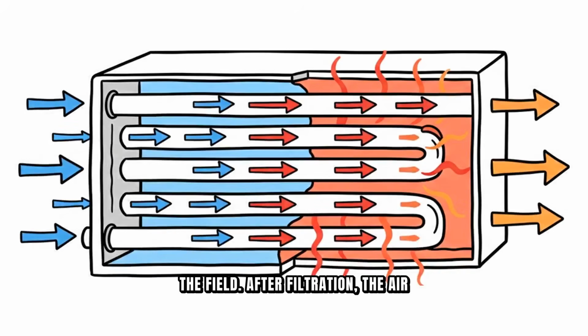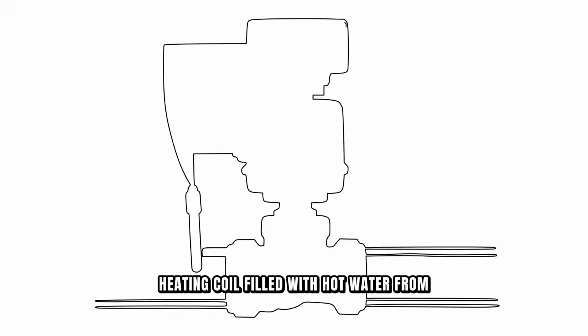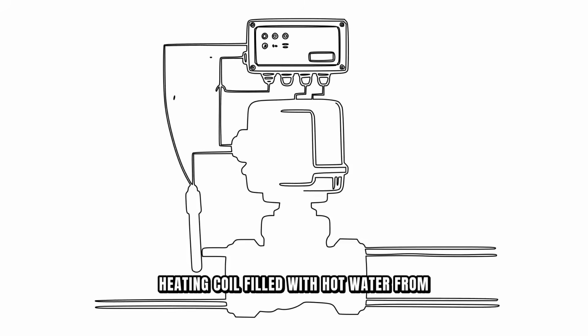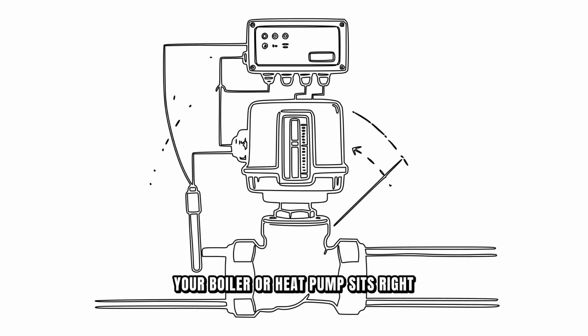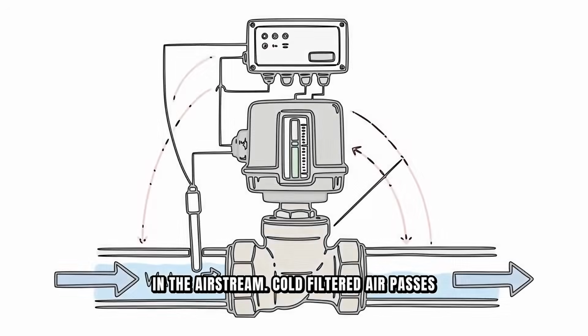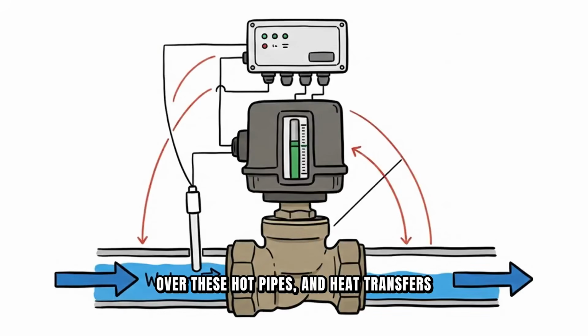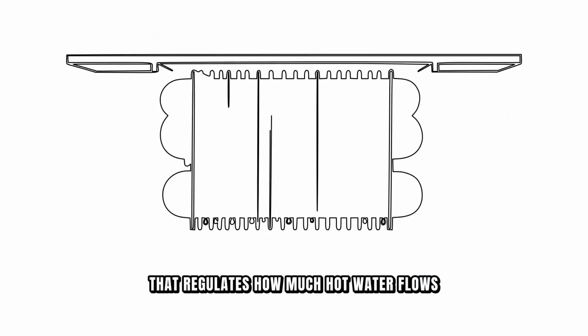After filtration, the air encounters the heat exchanger and cooling coil. Let's talk about heating first. In winter, a heating coil filled with hot water from your boiler or heat pump sits right in the airstream. Cold filtered air passes over these hot pipes, and heat transfers directly into the air. The amount of heating is controlled by a valve that regulates how much hot water flows through the coil.